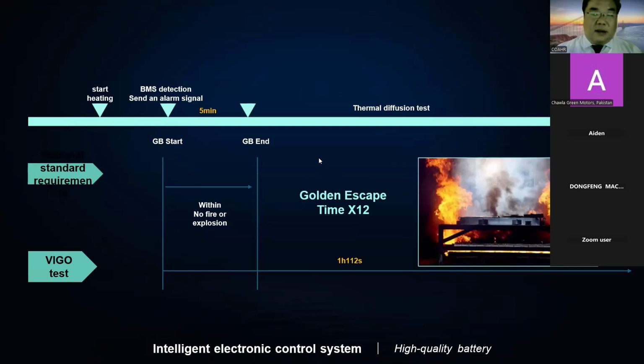In the thermal diffusion test, the battery starts heating and the BMS (battery management system) detects abnormal conditions and sends an alarm at 5 minutes. The battery then goes through the full GB test cycle, China's national standard, and still achieves an escape time over 1 hour 12 minutes without fire and explosion, far exceeding the Chinese standard requirement. In short, VIGO's thermal diffusion performance, BMS, and structure ensure exceptional battery safety, giving the user plenty of time to react to emerging situations.